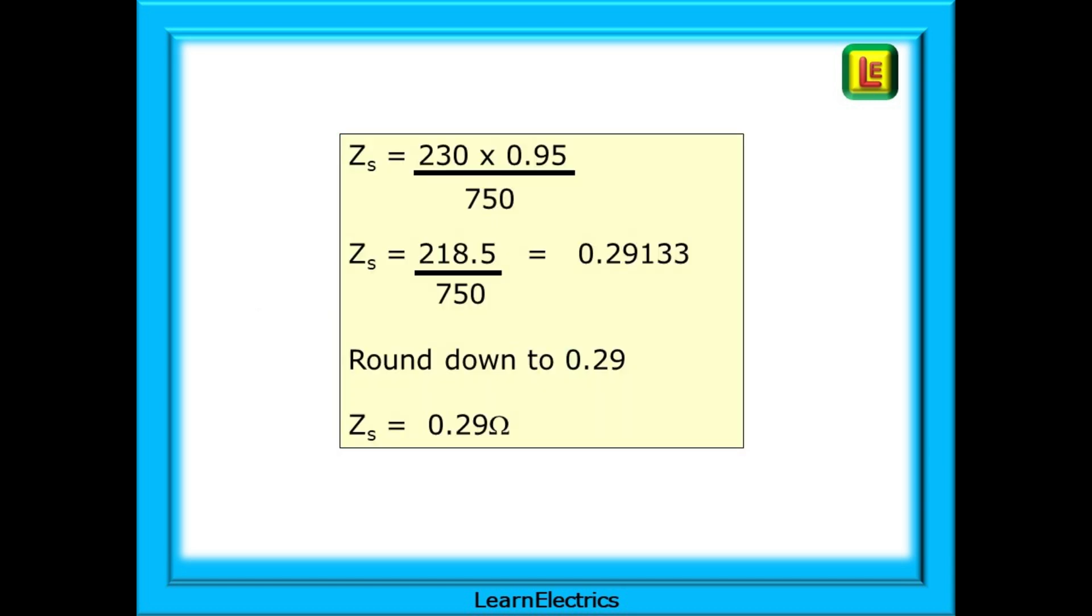Putting the numbers into the equation, we have 230 volts multiplied by 0.95 and then divided by Ia, which in this case is 750 amps. The calculator gives us 0.29133, which we can round down to two decimal places to arrive at 0.29. Ohm's law tells us the voltage divided by current will give us ohms. So, our answer is ZS equals 0.29 ohms.